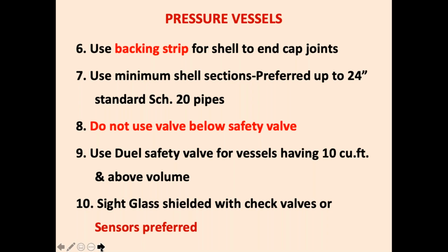This is another issue. 70, 80, 90, more than 90% people use stop valve. And when I ask them why are you using a stop valve, they say, sir, the safety valve leaks. So use a proper safety valve, calibrate it, and don't use a stop valve below the safety valve.